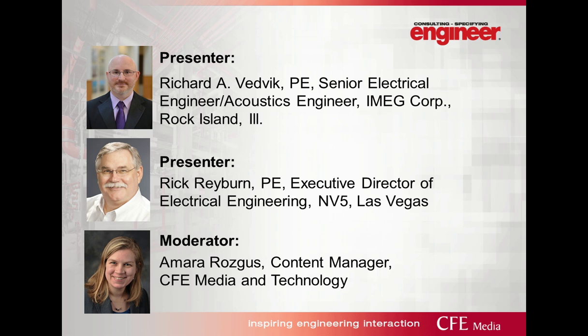The problem with it being classified as emergency power is the fact that it's not a separate wiring system that's self-contained and deemed to comply with all the requirements of Article 700. So the generator is not acting as an emergency generator. It's acting as a standby generator for optional power requirements.